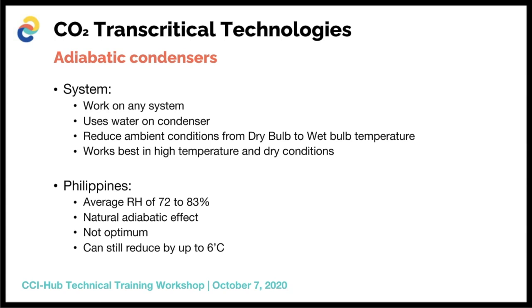Within the Philippines, the relative humidity is quite high. On average, you're looking at a relative humidity of 72 to 83%. So the Philippines basically has a natural adiabatic effect, and that's why we see a very constant temperature through the Philippine regions. This does, however, lead to adiabatic condensers not having such a massive impact as they will have in dry ambient conditions, which is the most suitable application for adiabatic and where the most benefits can be obtained. But you can still have your ambient conditions reduced by up to 6 degrees Celsius. So if there's water available freely or reclaimed to be utilized within these adiabatic condensers, you can have an additional 10 to 15% energy saving by utilizing adiabatic condensers.